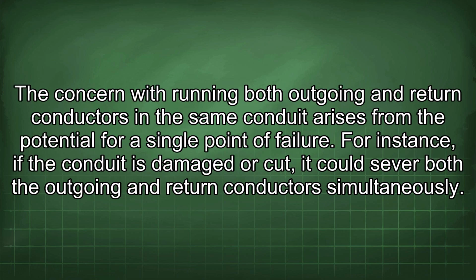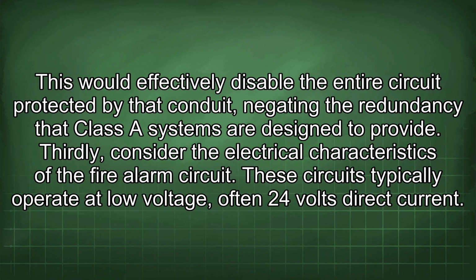The concern with running both outgoing and return conductors in the same conduit arises from the potential for a single point of failure. For instance, if the conduit is damaged or cut, it could sever both the outgoing and return conductors simultaneously. This would effectively disable the entire circuit protected by that conduit, negating the redundancy that Class A systems are designed to provide.